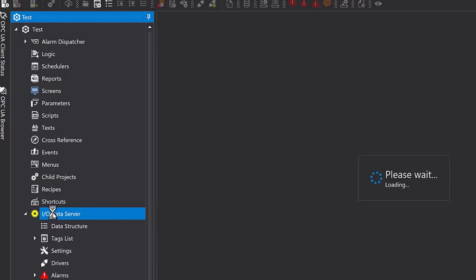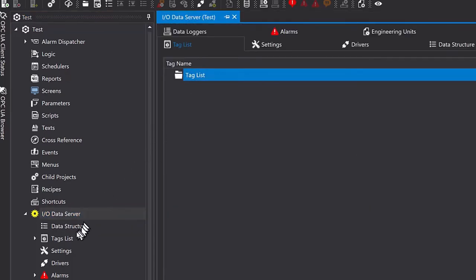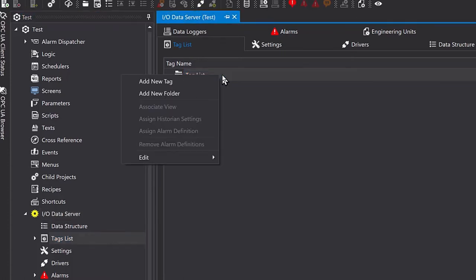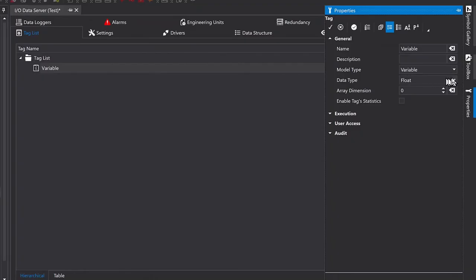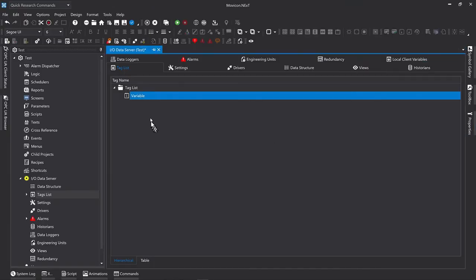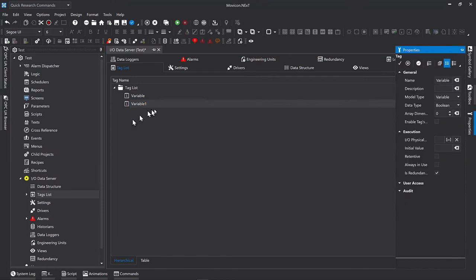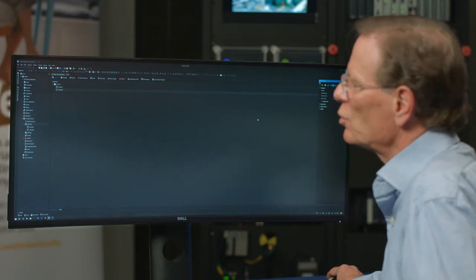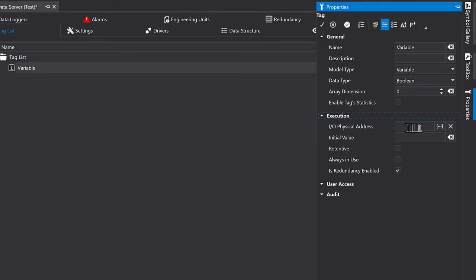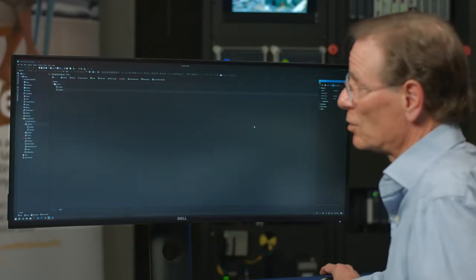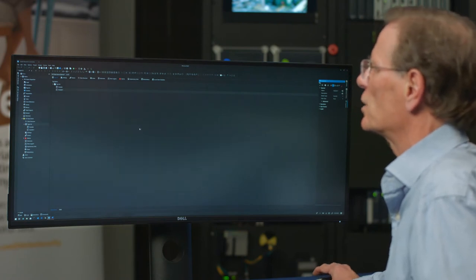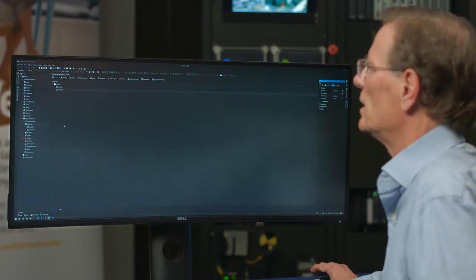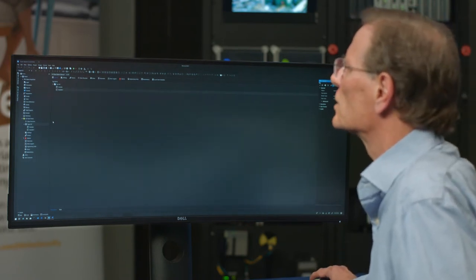I'm going to click into the IO data server. And in the IO data server, there's a tag list. I have the tag list and I'm just going to add a new tag. Now for this particular demonstration, the first tag that I want, I would like it to be a Boolean tag rather than a floating point tag. So I'm just going to make that change. So now I have a Boolean tag that I've created. I'd like to create one more. I'm going to leave it as a floating point. That's going to represent the value in a tank itself. If I was connected to the plant floor equipment, I would actually be able to put in the address either as an OPC variable or other mechanisms that ties it to the PLC that actually is managing that piece. But for now, I've just made these as local variables within my screen itself. That's really all I need to do to create the variables that I'm going to use.